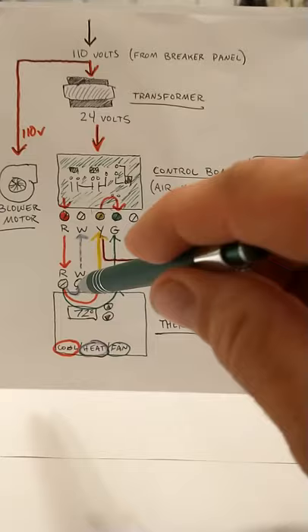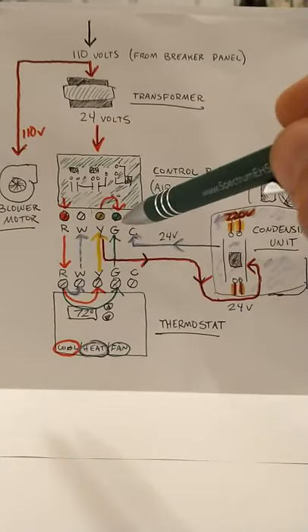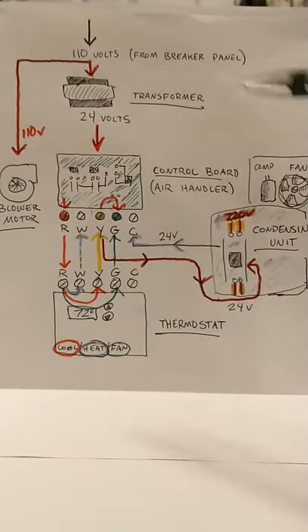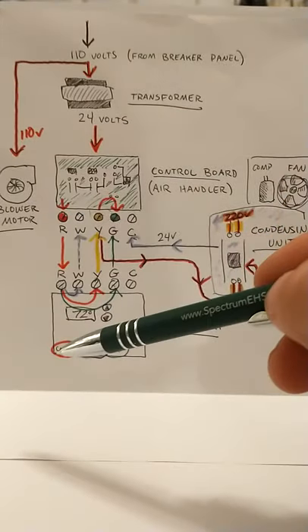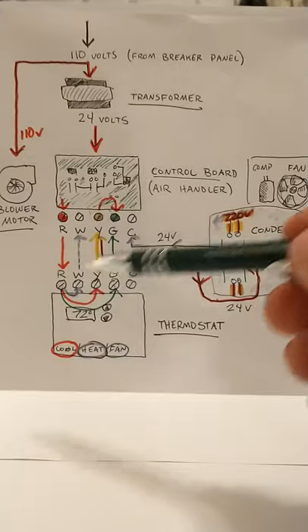You'll have one cooling system with a transformer that creates 24 volts. And then you'll have a completely separate heating system, which also has a transformer that generates 24 volts. And you don't want to put them both together in the same terminal. So you separate them.